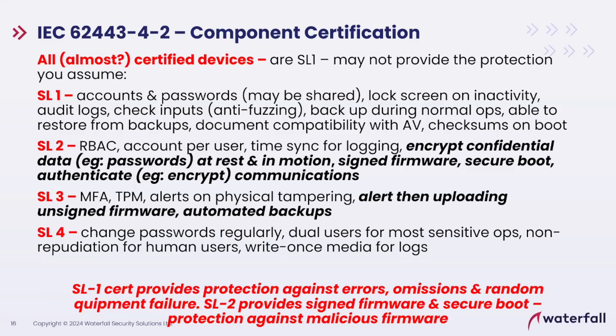If all you have is an SL1 device, your connection to the device is not required to be encrypted. The ability to load new firmware into the device, like all zeros, bricking the device, is not required to be password protected. The device is not required to reject the firmware because it hasn't been signed. Advanced security features are not there. It's the very basics that you're getting.